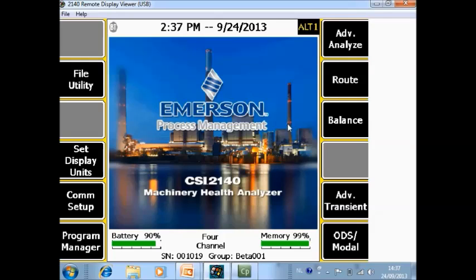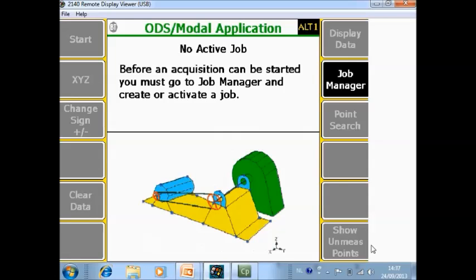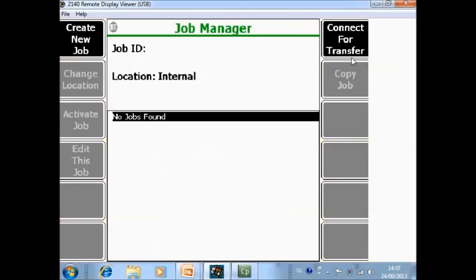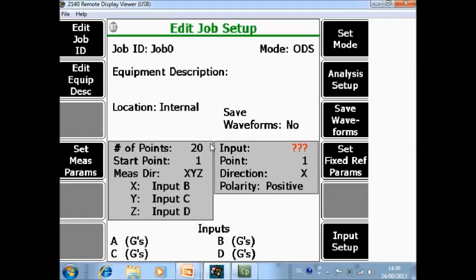What you are seeing now is the home screen of the CSI 2140 Machinery Health Analyzer. The first thing we will do is create an ODS/modal job, so go to F12 ODS/modal. Go to F8 job manager and we will create a new job. It has the name job 0 — if you want, you can change it. With F7 we can toggle between ODS or modal. In this example we will configure an ODS, and here you first have to specify the input sensor. Go to input sensor and specify that the reference — the fixed sensor — is on channel D, on the first point in the X direction with a positive polarity.